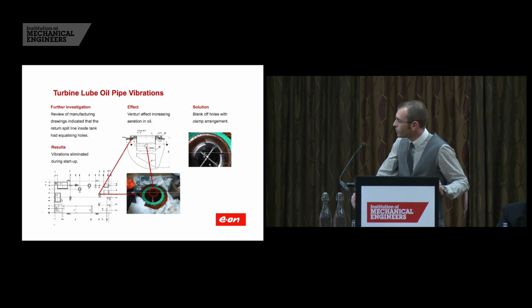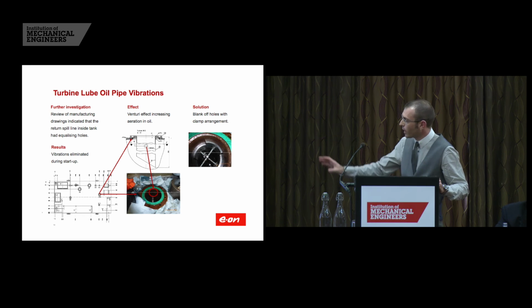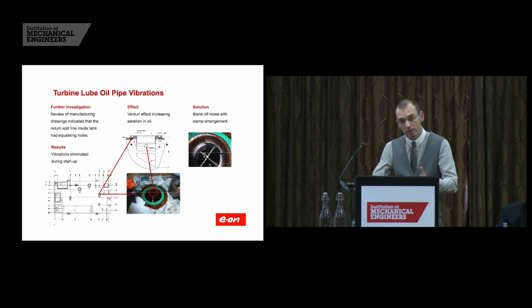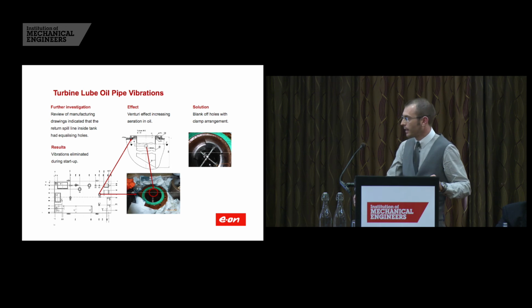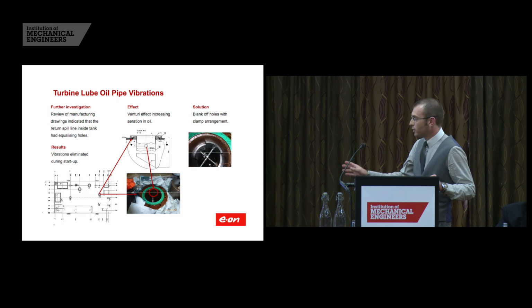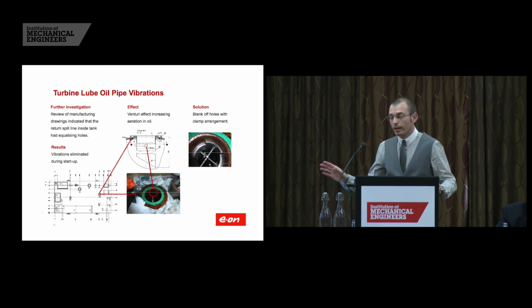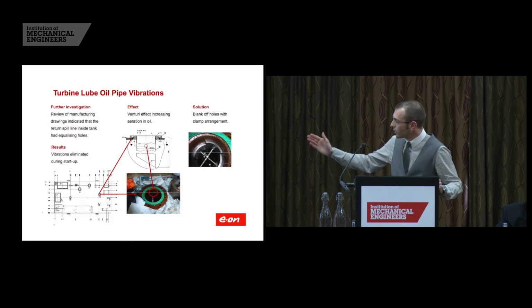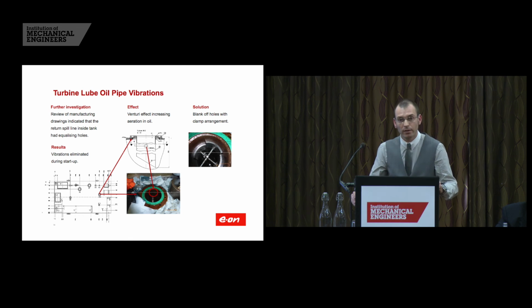What we have is return lines to the oil system. Many of the return lines are not fully charged, as many of you are aware, and when the oil goes into the tank, we have aeration holes. However, we have a main spill line, so when both pumps are in operation, any excessive oil is returned back to the tank. However, this pipe should not have had these holes in. Now, on the manufacturing drawing, the holes are clearly present, so they were actually manufactured and installed.